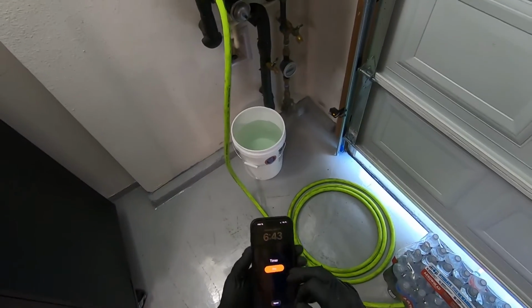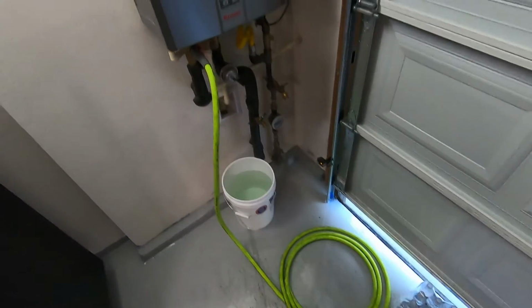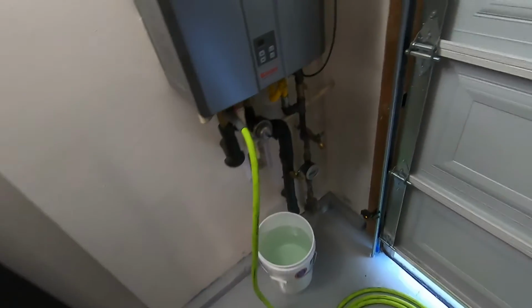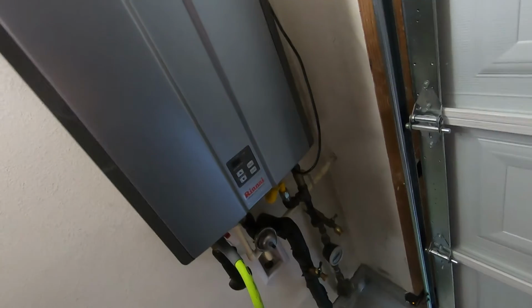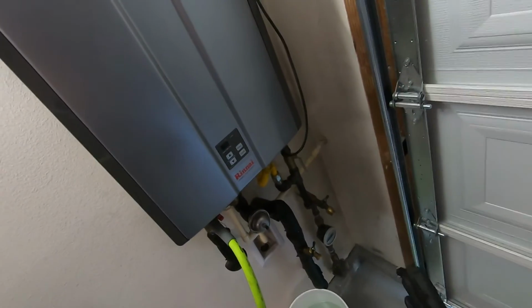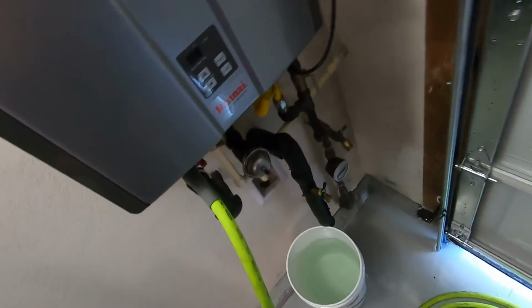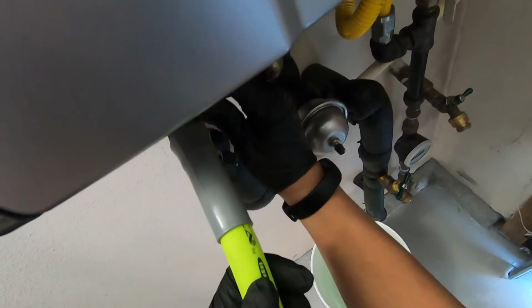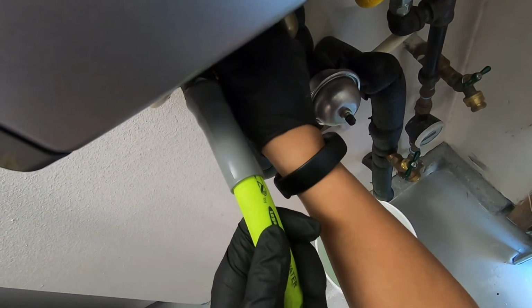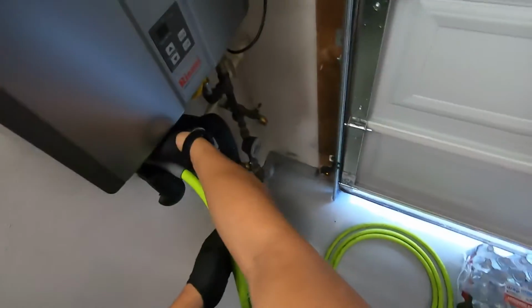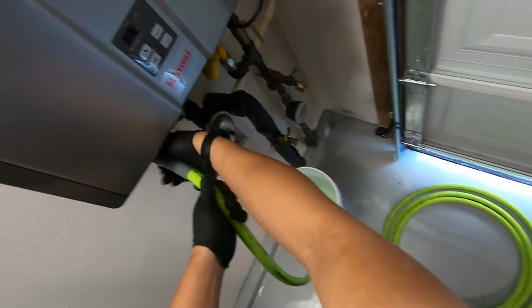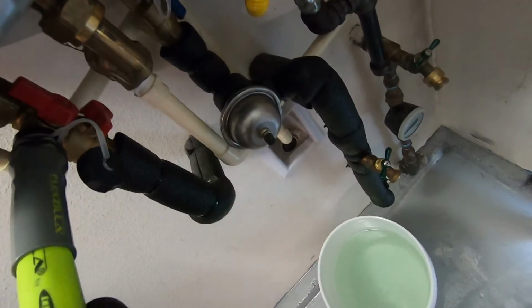All right, so our 5-minute timer is up. We've now flushed all of the vinegar, or the flushing solution, inside the heat exchanger. So we can now shut off the port. Then we can disconnect this line right here.